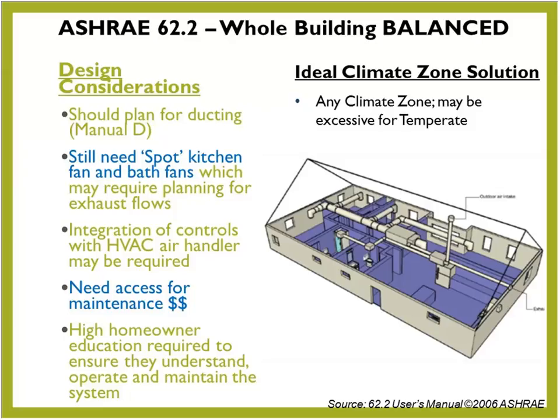So here's a picture of that install, and you'll see that now we've got the furnace there, and we've got an additional piece of equipment to the right, that little small box with the stack on top of it. And it's running actually to the bathrooms, and this application, which I'm not crazy about, is also being used as your exhaust ventilation for showers and whatnot. Again, I'm not crazy about that approach, because if we install a 150 CFM ERV or HRV and lose 10% of it to performance or to the ductwork, by the time you split it up in a bathroom or maybe a laundry room, the amount of air coming out of each of those pickups is maybe not ideal to exhaust the moisture quickly enough to satisfy the homeowner.